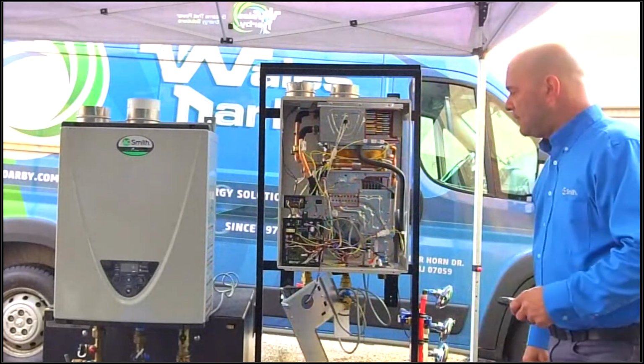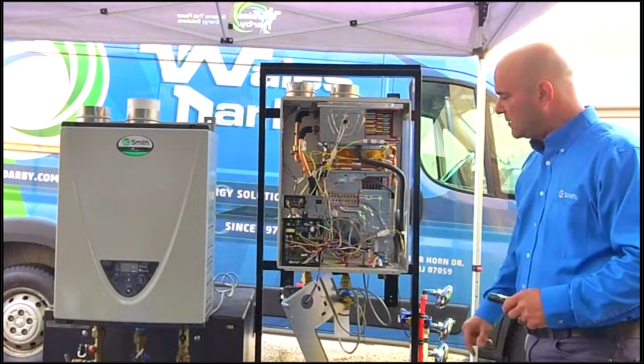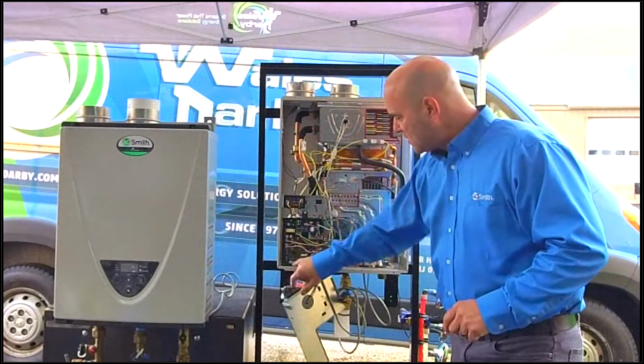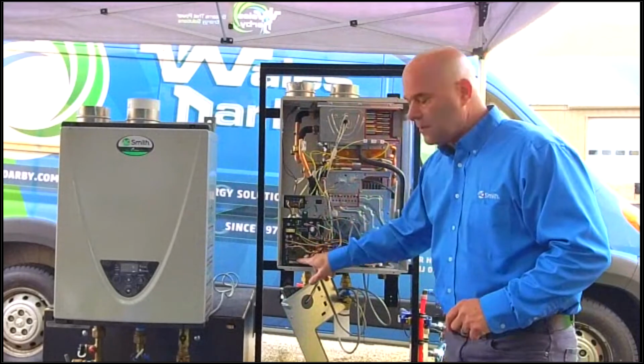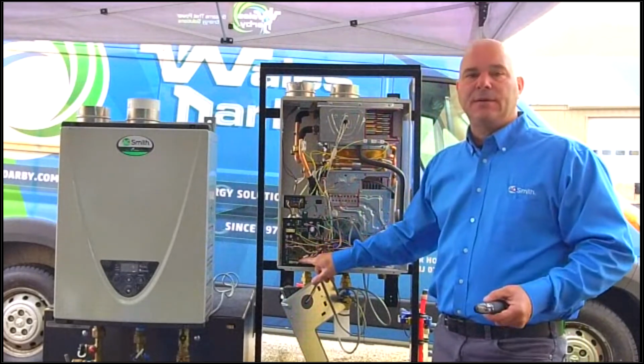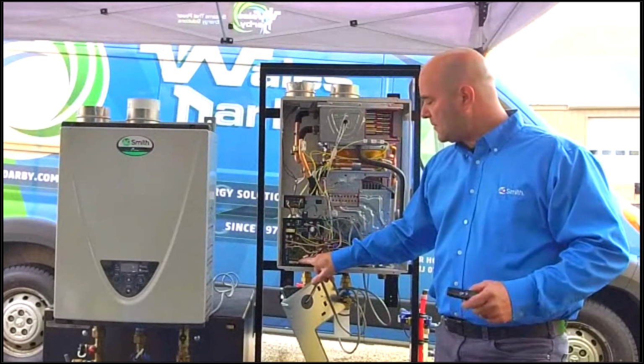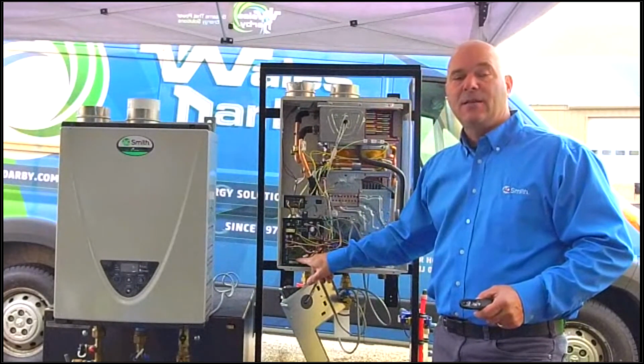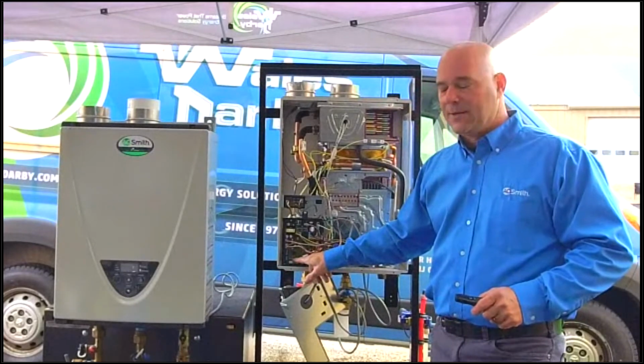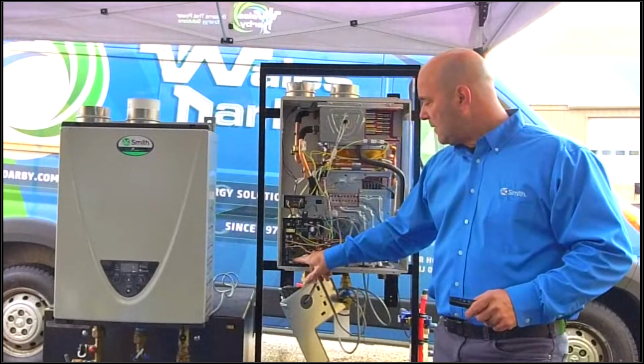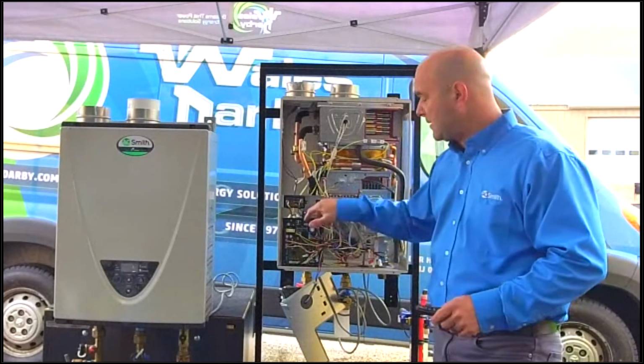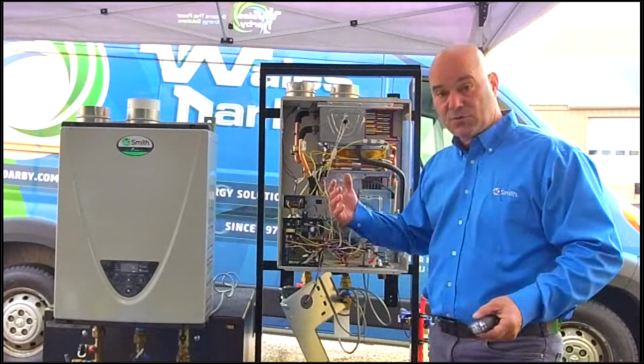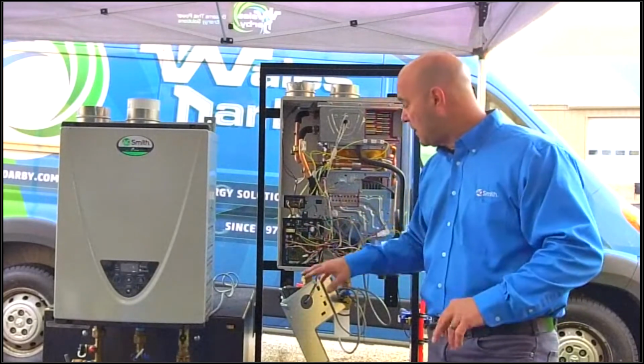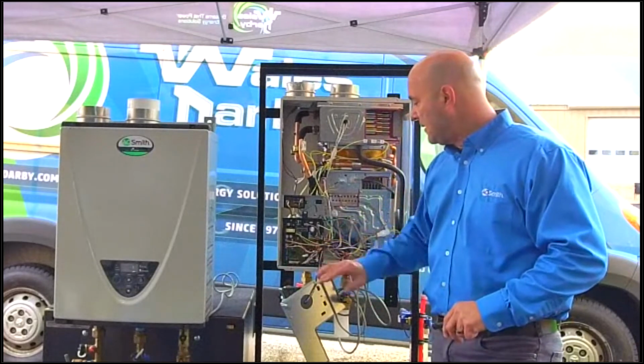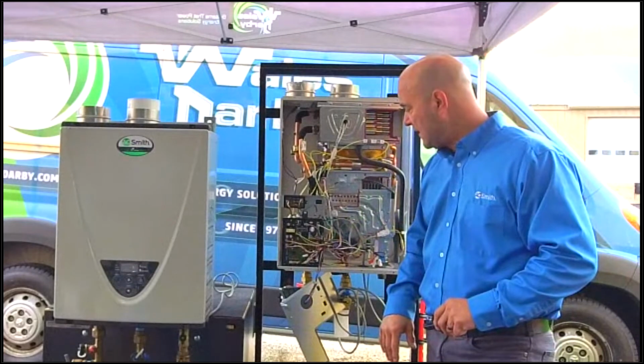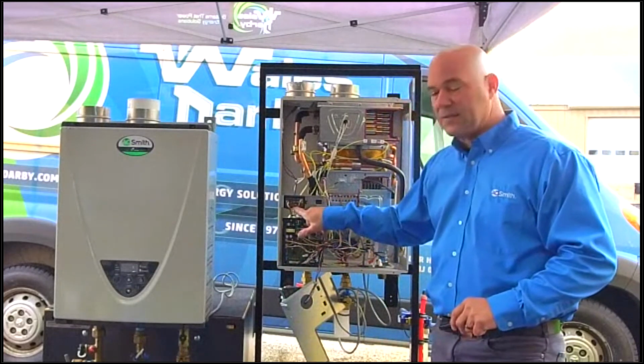The control itself, pretty robust. It's coated, so it's kind of waterproof. Dip switches, 4 little black buttons down here along the bottom. If you're ever in the field and you're having a problem with combustion, you're on the phone with A.O. Smith, we have the ability to adjust the gas. We also have the ability to reset a hard lockout here by pushing the buttons. It'll reset a hard lockout. Any of the soft lockouts, majority of the lockouts you'll be able to do with the on-off button. But if it's in a true lockout, it says I'm not going anywhere. We're going to go to button 3 here and push that. Hold it in about 3 seconds. It'll reset it.